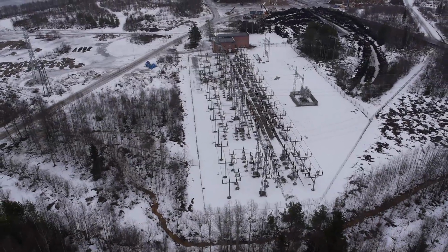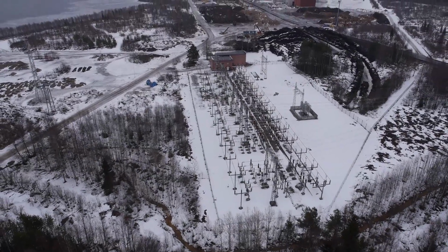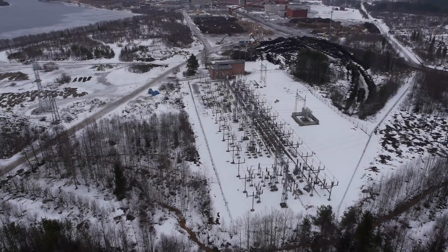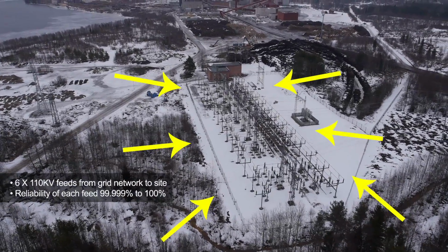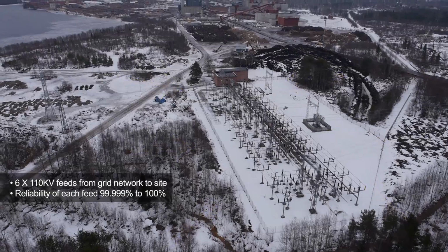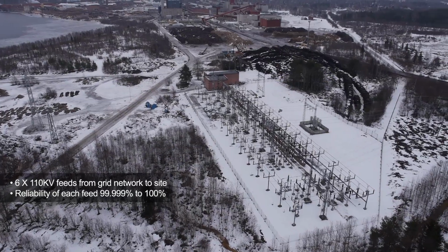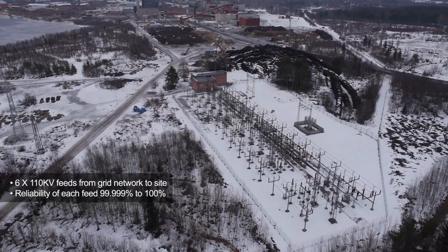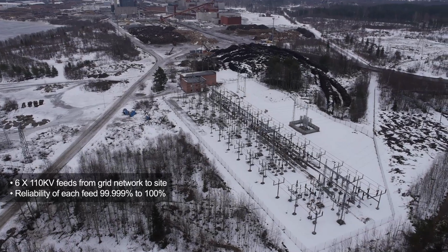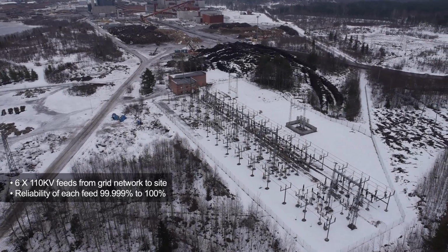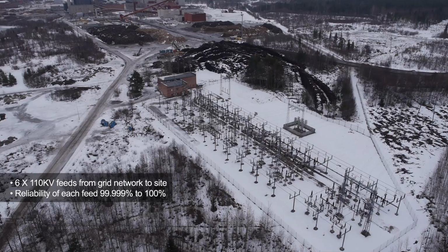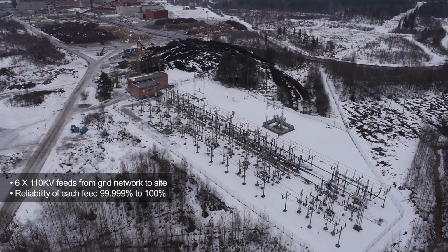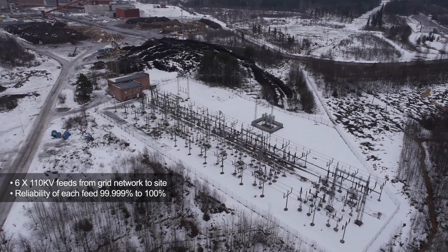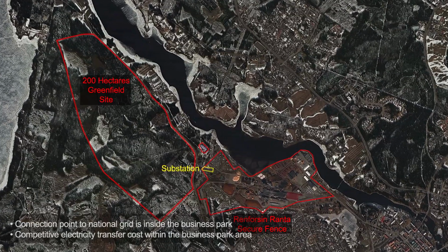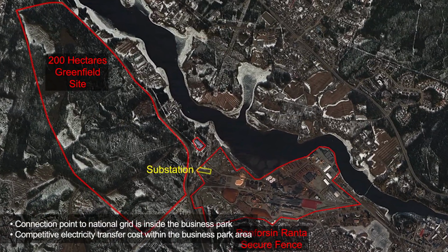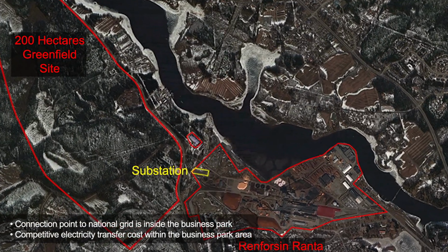Renforsin Ranta's power delivery infrastructure is world-leading in terms of reliability. There are 6 separate 110 kilovolt electricity feeds coming from the national grid network into the site, with the reliability of each being from 99.999% to 100%. The last power delivery outage experienced in this area of Finland was in 1981, and it lasted only 15 seconds. The National Grid substation is located within Renforsin Ranta's security fence.